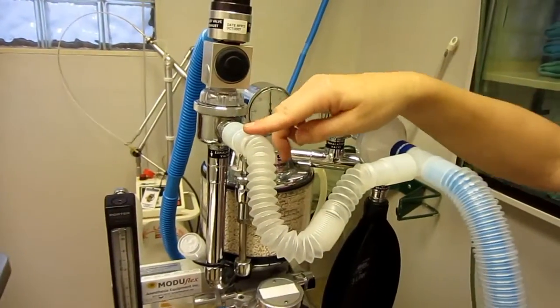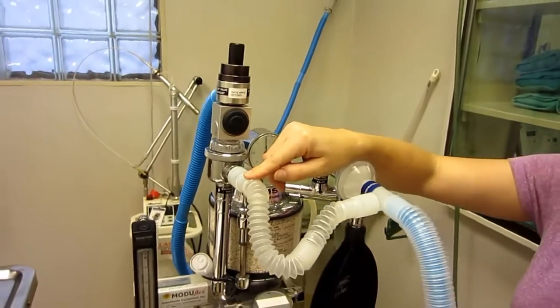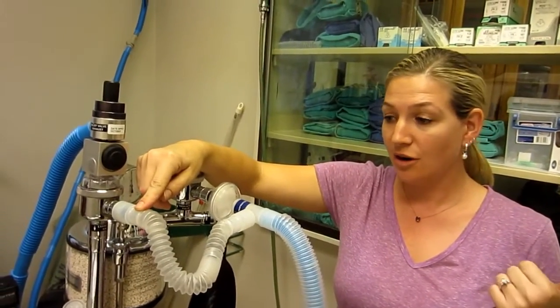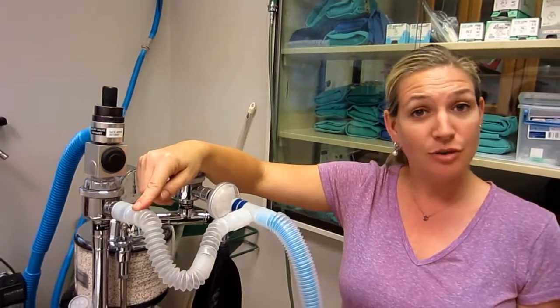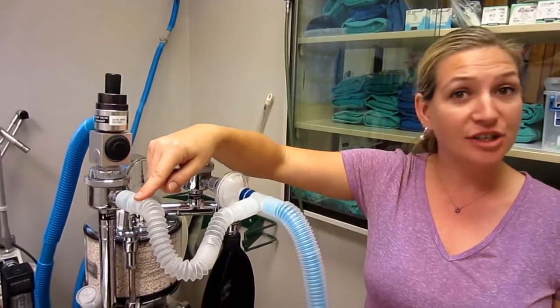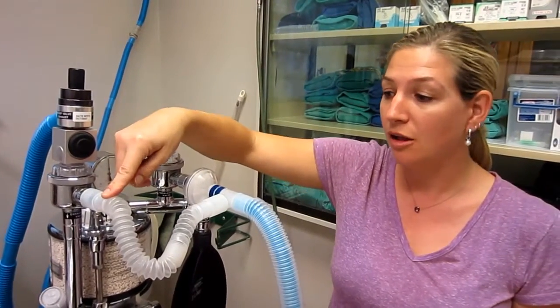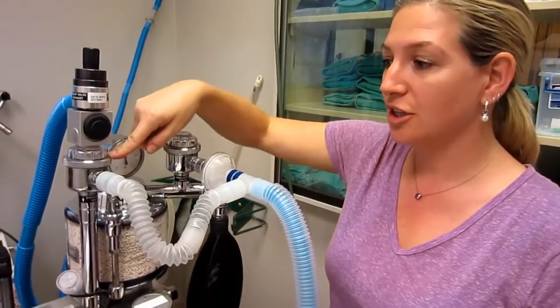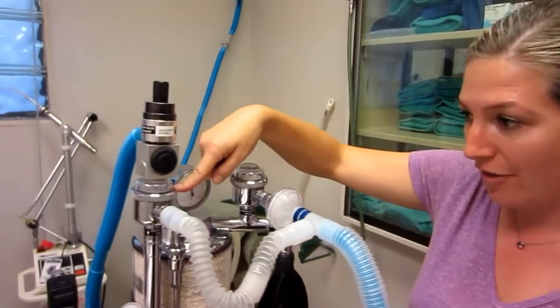And at this point, I should mention, it is no longer oxygen and isoflurane gas. It's CO2, or carbon dioxide, and there may be a little oxygen mixed in there as well. All of that has been exhaled, and now we get to the unidirectional exhalation valve.